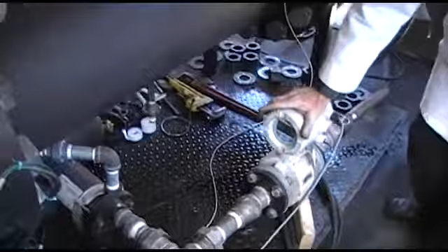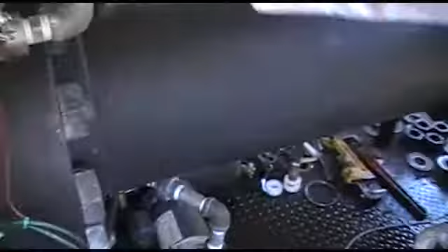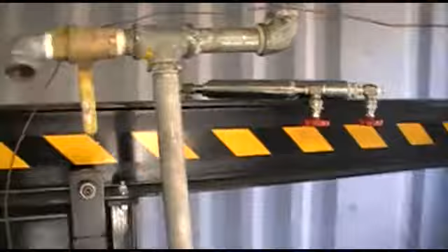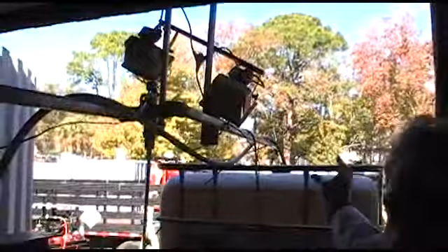We have a known volume of water. We're passing it through the vessel and then right back into the container again, and we measure the temperature rise over time of this water, and it gives us a direct reading in BTUs. Now, in the process, we have two pumps underneath. We have one flow meter, which measures the flow rate of the water. We have thermocouples measuring the output temperature of the water, some analog gauges also measuring the water, and another thermocouple measuring the water in the tote.